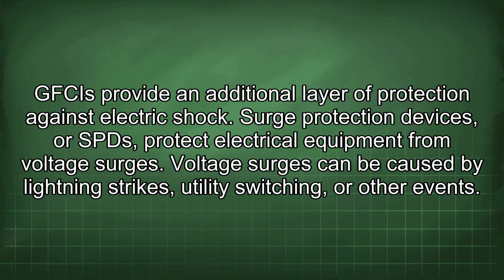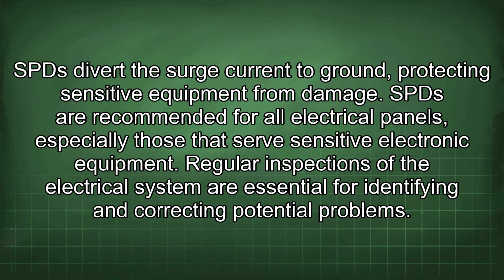Surge protection devices, or SPDs, protect electrical equipment from voltage surges. Voltage surges can be caused by lightning strikes, utility switching, or other events. SPDs divert the surge current to ground, protecting sensitive equipment from damage. SPDs are recommended for all electrical panels, especially those that serve sensitive electronic equipment.